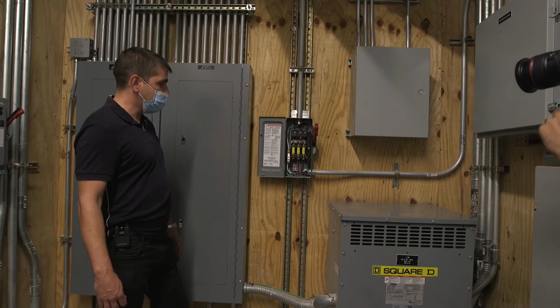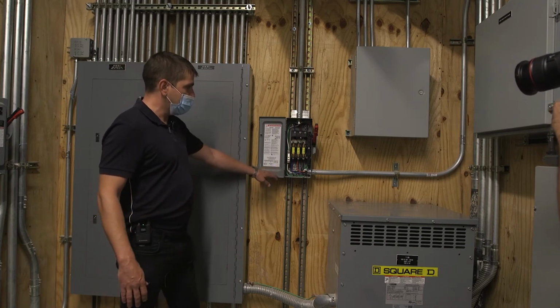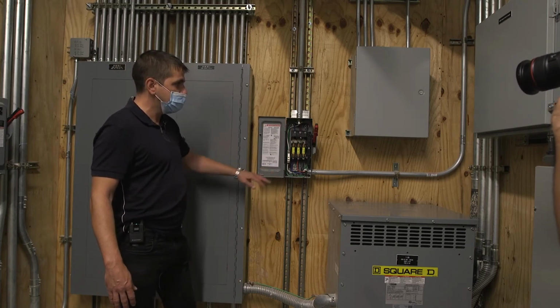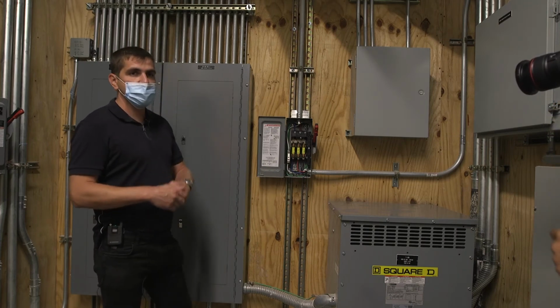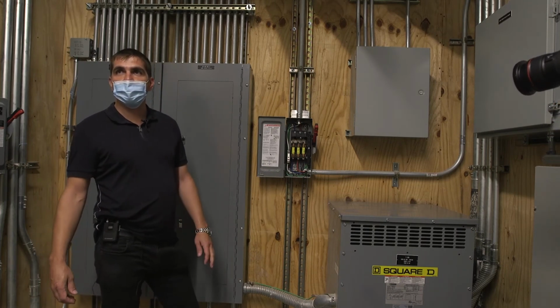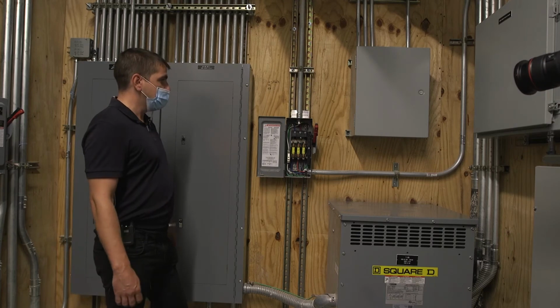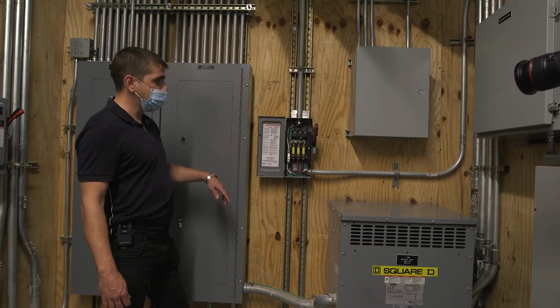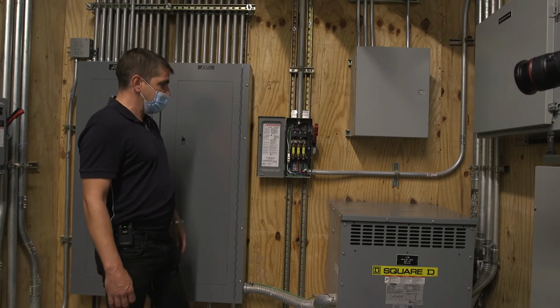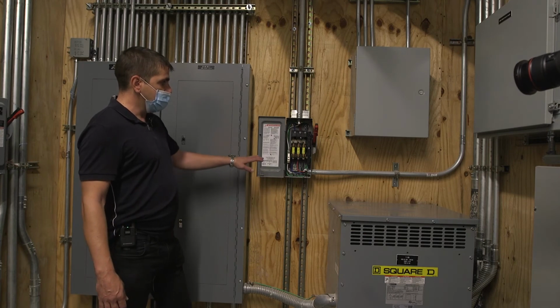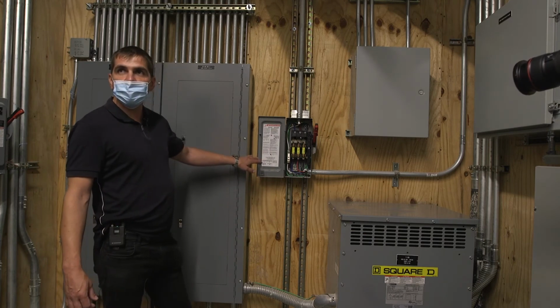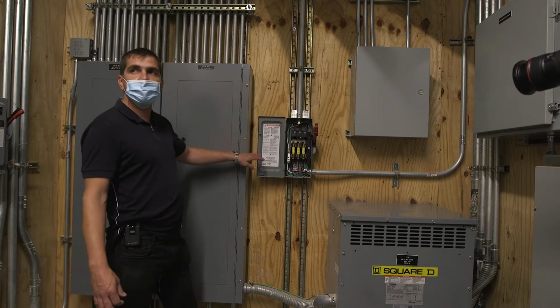So in case the fuse is burned and the power is not being supplied, most likely the cause is going to be some short circuit downstream from the fuse disconnect. It has to be verified first. Then any work performed on the fuse disconnect, including replacing the fuses, has to be done in a de-energized condition.